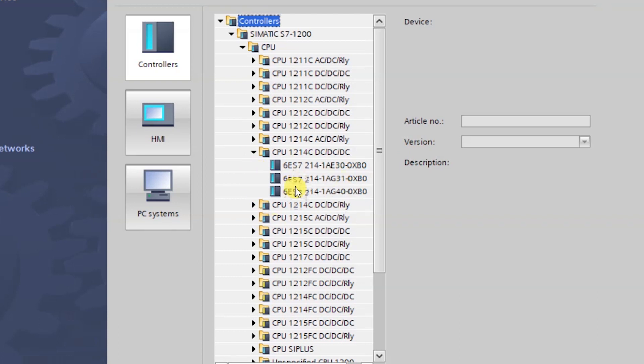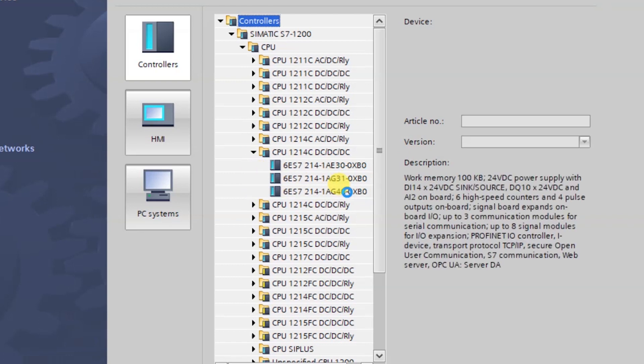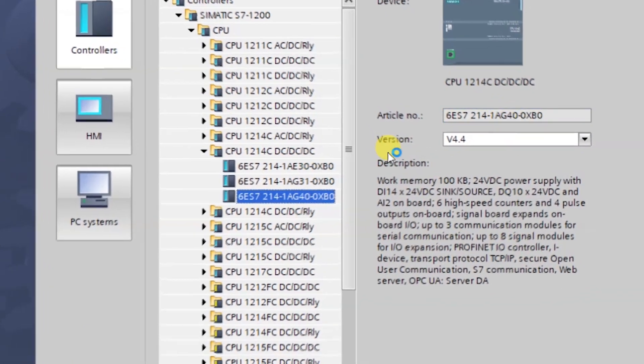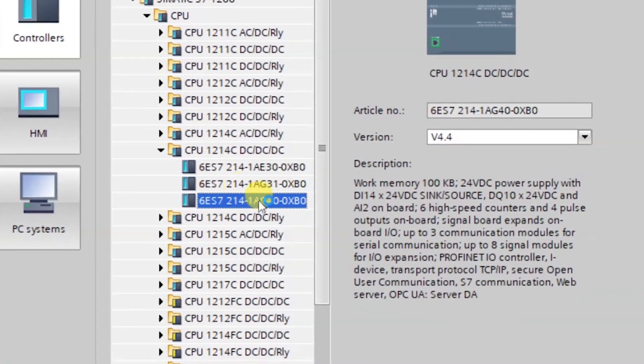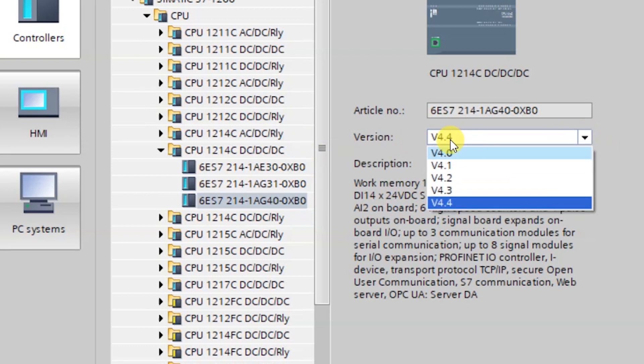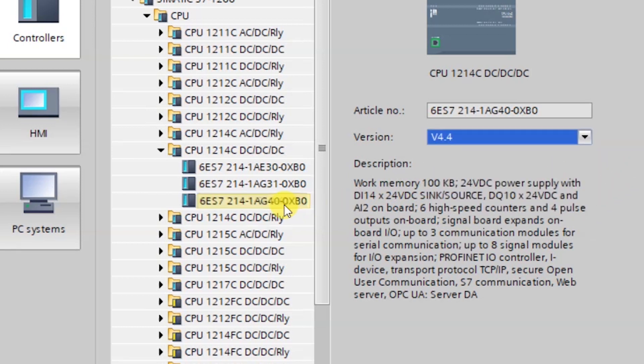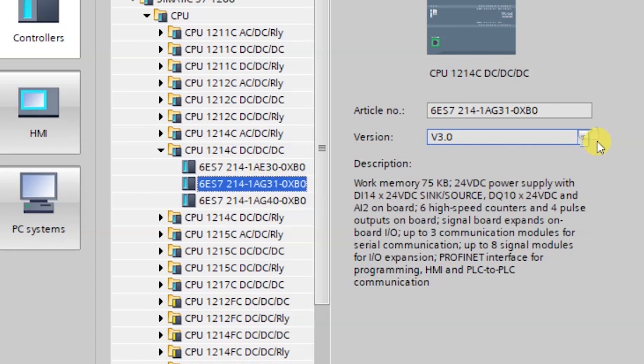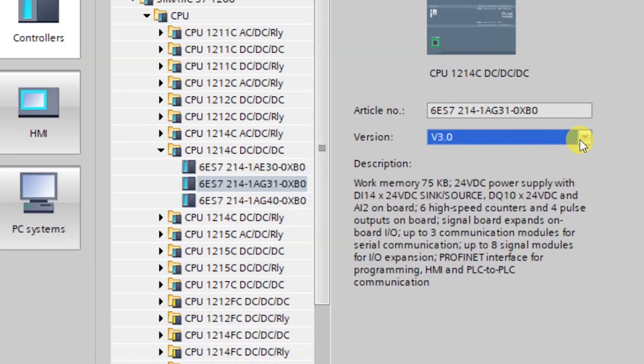I have this CPU which is AG 40, and in this CPU the firmware is 4.4 and the least possible firmware is 4.0. So that means we can take full upload from this PLC. But what if I have the CPU AG 31? This CPU has only one firmware version, that is 3.0, so we cannot take upload from this CPU.